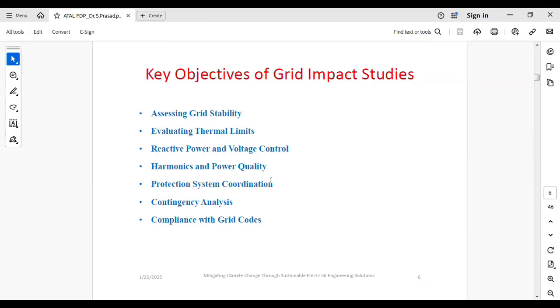Similarly, harmonics and power quality studies also have to be conducted, because as you know, in PV plants we are using inverter based renewable sources, IBR systems, inverter based resources. Since inverters, which are power electronics based converters, are present, there is a possibility of injection of harmonics into the grid. So how much percentage of harmonic distortion, THD value, of current harmonics or voltage harmonics can be injected is governed by the IEC guidelines, which we have to follow. So before interconnection, these are the studies we are conducting.